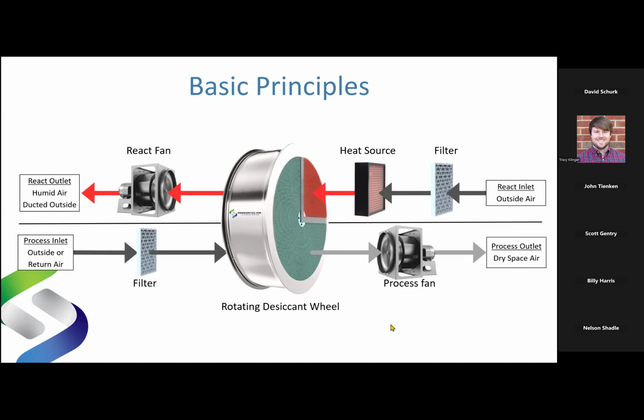And it just is so efficient and so elegant and works so well and is so simple when you understand what's going on, okay? Now, this heat source is thermal energy. I have to have an input. There is no free thermodynamic lunch. And I'll talk more about that in the next slide. But this heat source can be electric. It can be gas. It can be steam. It can be hot water. It can be waste heat. If you have waste heat at the right temperature, dehumidification is basically free. This is the largest energy consumer in a desiccant dehumidification system. It's this heat source, right?